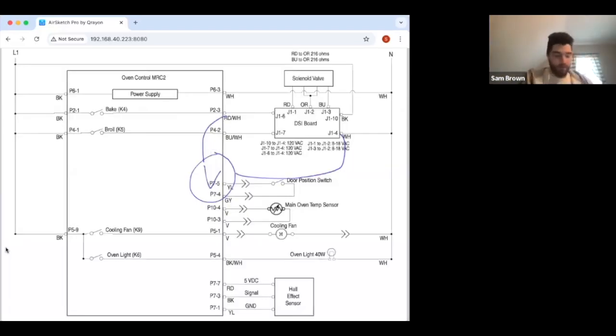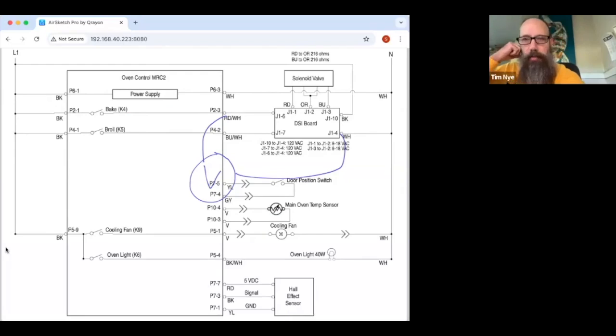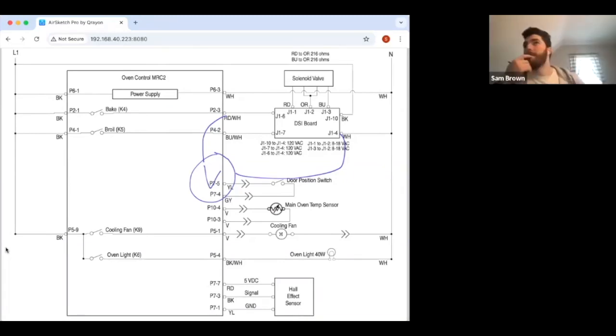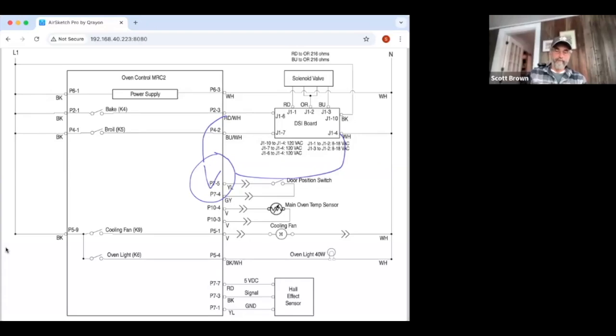So we know the DSI board is working properly. Again, with that and the temperature sensor both being good, that only leaves the main control board, really. Which makes me wonder if the actual temperature sensing component of the board was not the failure part. Do you see what I'm saying? That would actually be a good thought. Yeah, good thought. That does happen - it's not an uncommon thing at all.